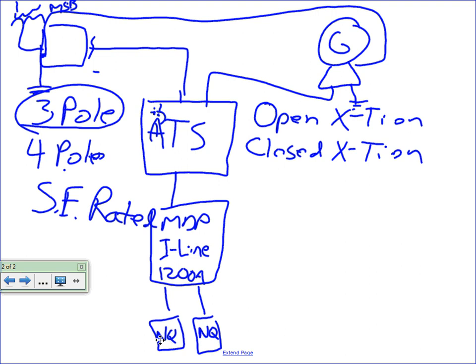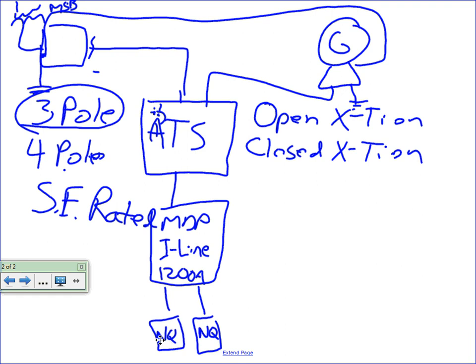Switchgear is built so everything's barriered from each other. The breaker compartment is at the very front, which is separated from the bus compartment in the middle. We provide barriers as an option to barrier the bus and cable compartment from each other, so each area is barriered from another. And we actually put side barriers in, so each section where you're making these cable connections is barriered from the adjacent section. That's number one. As you look, the breakers are in the front, all the terminations in back.